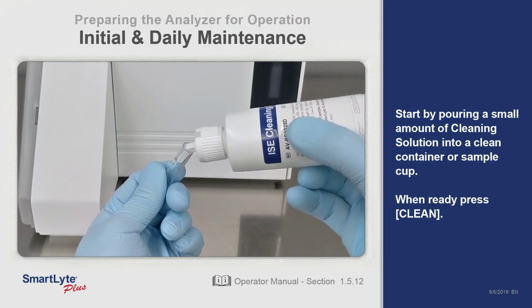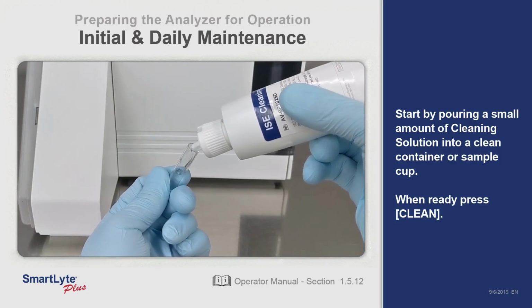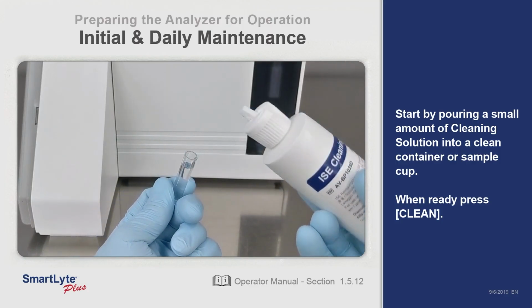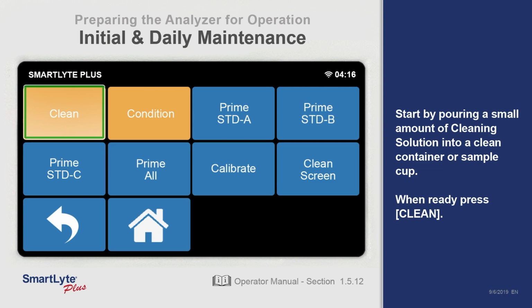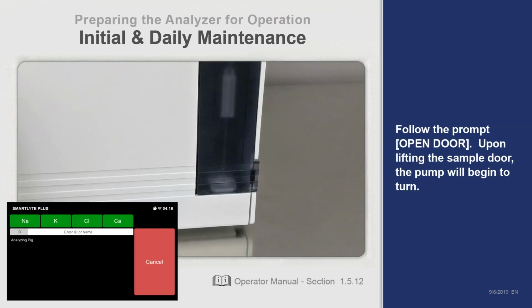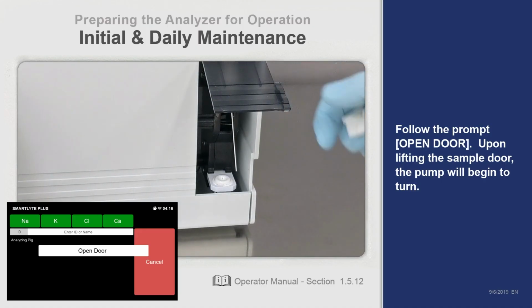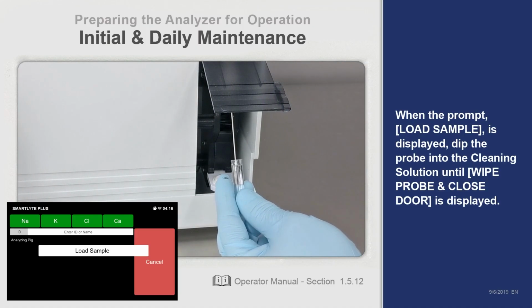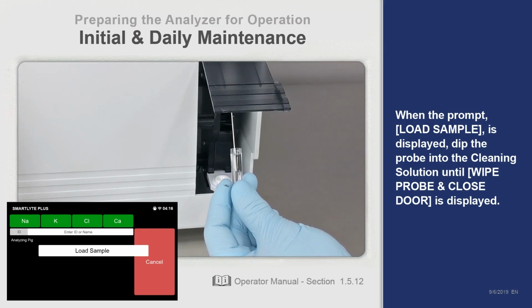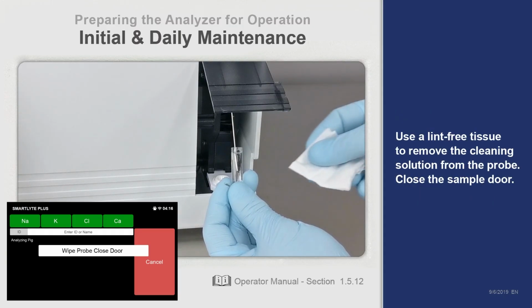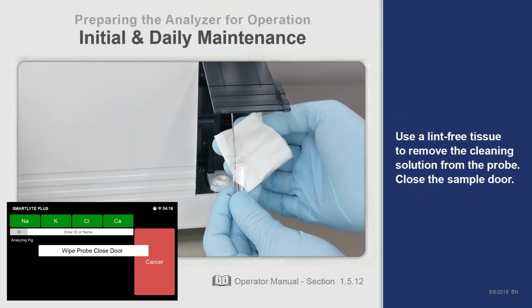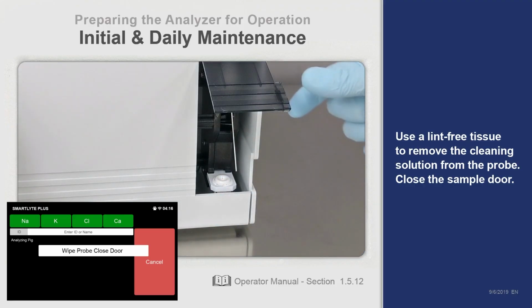Start by pouring a small amount of cleaning solution into a cleaning container or sample cup. On the display, press Clean. Follow the prompt Open Door. Upon lifting the sample door, the pump will begin to turn. When the prompt Load Sample is displayed, dip the probe into the cleaning solution until Wipe Probe & Close Door is displayed. Use a lint-free tissue to remove the cleaning solution from the probe and then close the sample door.